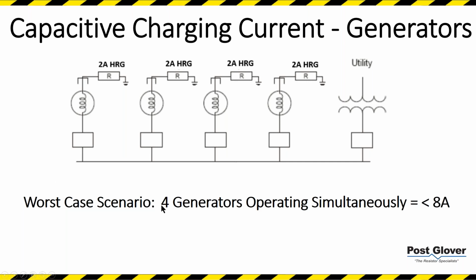But that's not usually a realistic example, because you don't parallel generators so that you will always run all 4 at the same time. So it's just simple math, right? You can go 3 generators, and if that's the worst case scenario, then you have to be under 6 amps. If you were just 2, you have to be under 4 amps. You get the idea. Then 1 would be the 2 amps. So you need to make sure this is a consideration you figure out.